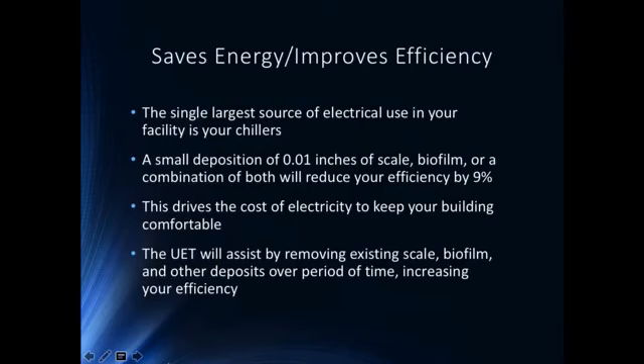Saving energy and improving efficiency obviously is huge. One of the other largest users of electricity, switching gears to electricity instead of water in your facility, is the chiller system that operates the HVAC. Typically, it is by far the single biggest consumer of electricity. And unfortunately, just a very small amount of deposition, 0.01 inches of scale or biofilm or some combination of any deposit, reduces the energy efficiency of that system by 9%. Again, that can be extremely significant from a dollar standpoint. This drives the cost of electricity up high to keep the building comfortable. And so by keeping constant free chlorine residual and precipitating the unstable minerals in the reactor, we keep those heat transfer surfaces clean and save energy.